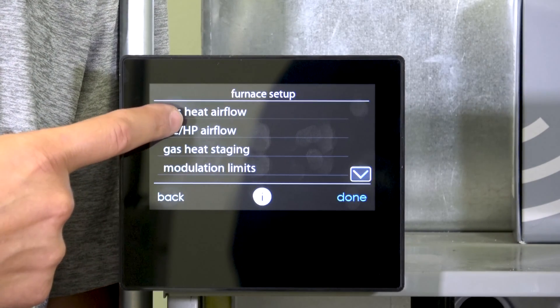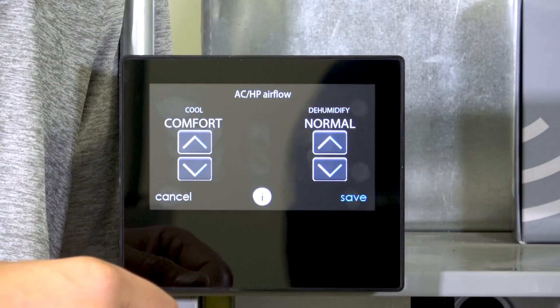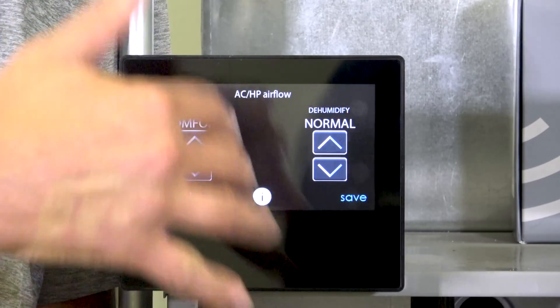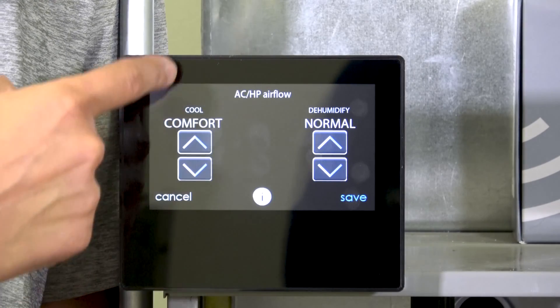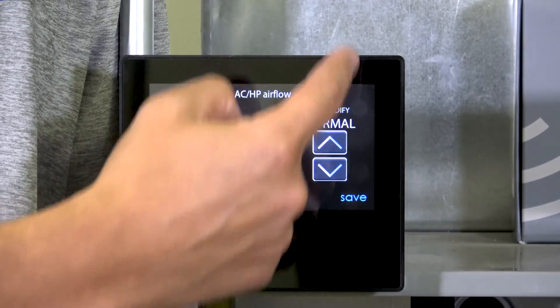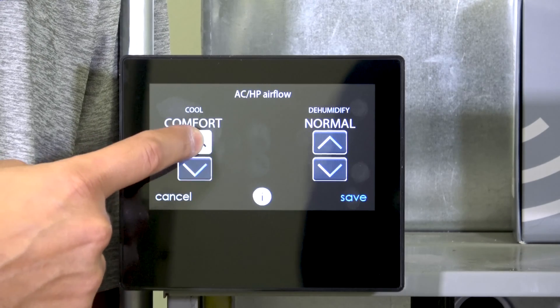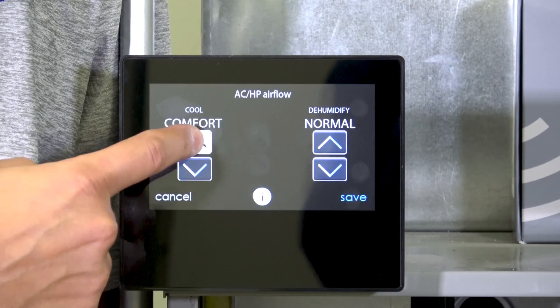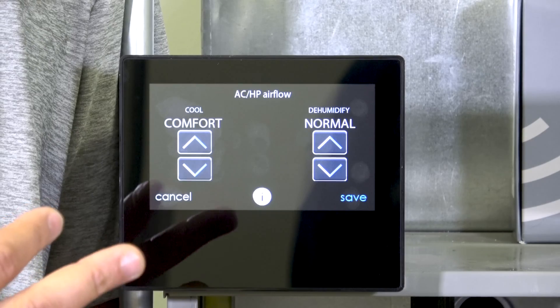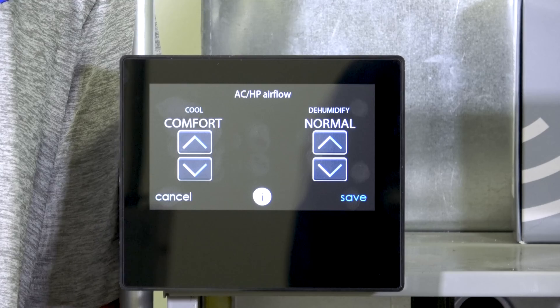The next one is AC heat pump airflow. Even though we're in furnace setup, this is AC/heat pump related because the furnace's blower is the fan used in AC mode — so I'm setting it up on the furnace circuit board. On the left is cooling airflow, in the middle would be heat pump if I had one, and on the right is dehumidification mode. For cooling airflow I have a few choices: Comfort, Efficiency, Max — sometimes you'll see five choices: Quiet, Comfort, Efficiency 325, Efficiency 350, and Max, depending on the unit connected.